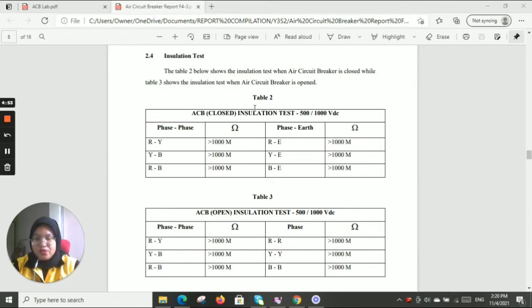Basically there are two situations we need to test: ACB closed and open position. In closed position there are phase-to-phase and phase-to-earth tests. Here you can see the resistance values are greater than 1000 megohms, which indicates the ACB is in good condition.